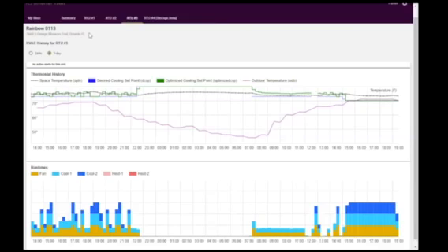And over here, we can see the green line, which is the optimized set point, is going up above the dashed space temperature line. What that ends up causing, for example, in this particular piece, is it forces the unit off. So we don't even need to control the unit directly.